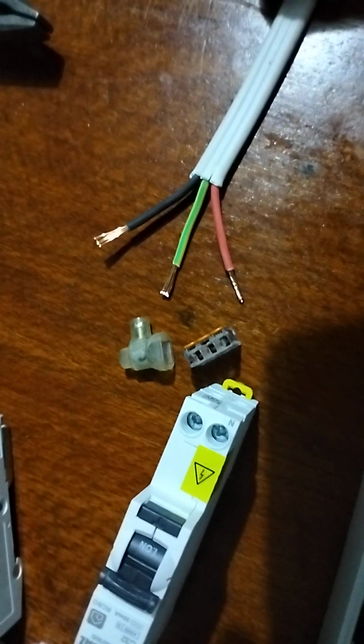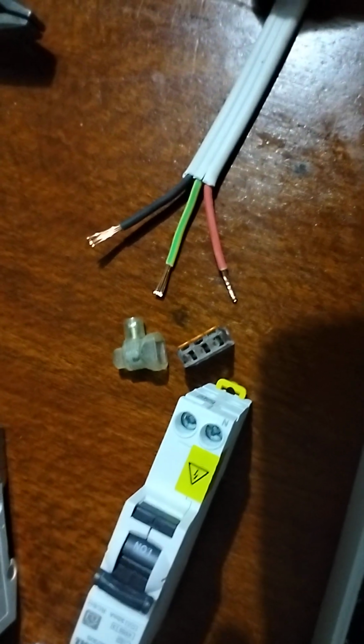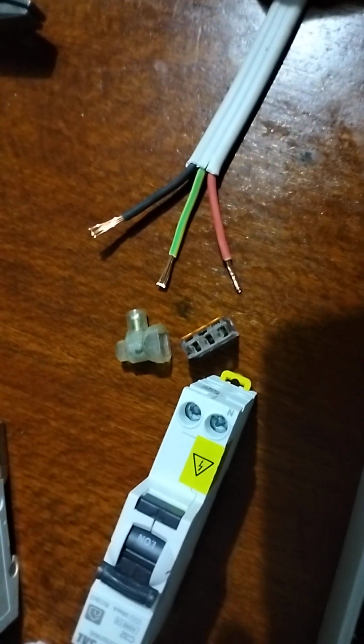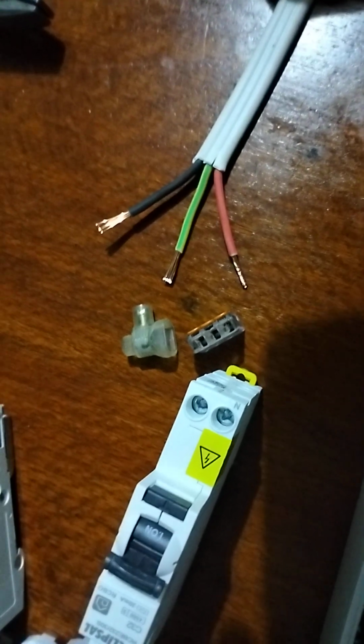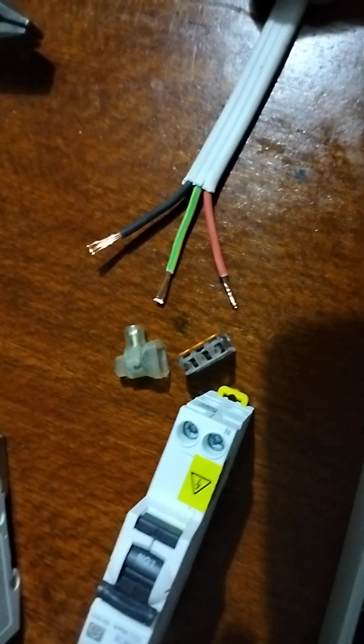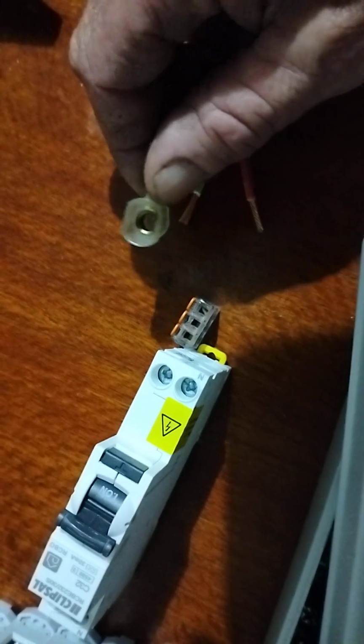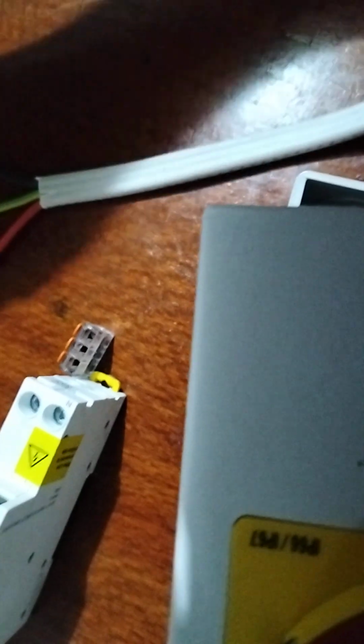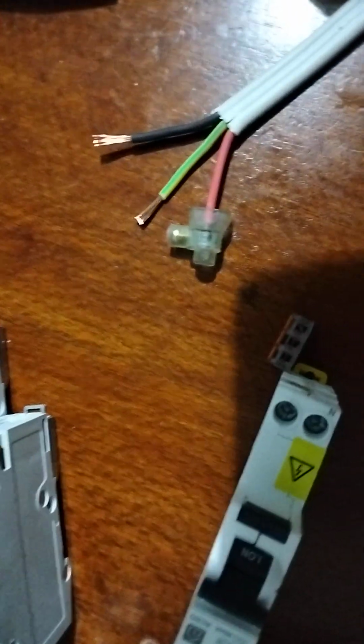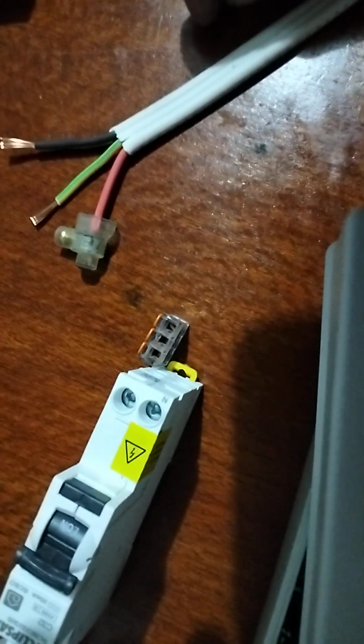A lot of them were Bakelite, and the earth connectors are a double screw version of that. Back in '74 the earth connectors were bare, but now they're insulated, with holes at both ends, whereas this one has a cap on one end and a hole on the other. So it sits like that, and you twist all the conductors together and screw it up tight. I've seen those well over 40 years, not a problem.